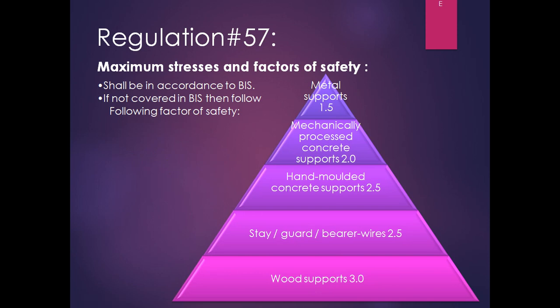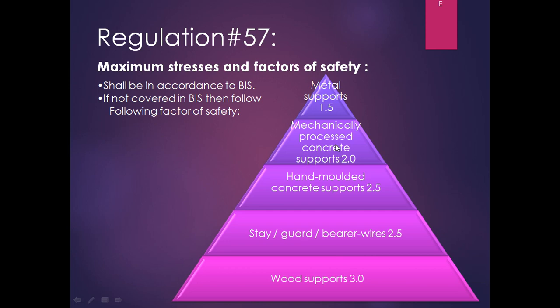Regulation 57 is regarding maximum stresses and factor of safety. It shall be in accordance with BIS. However, if not covered in BIS, we have to follow the following factors of safety: for metal support, minimum 1.5; for mechanically processed concrete support, minimum 2; for hand molded concrete support, minimum 2.5; for wooden support, minimum 3.0; and for stay wire, guard wire, and bear wire, minimum 2.5.